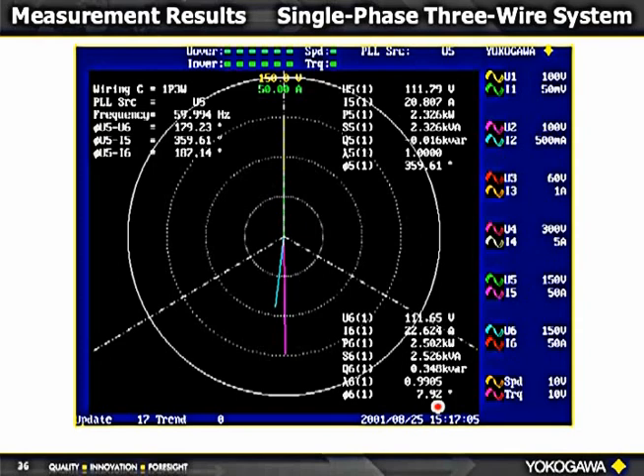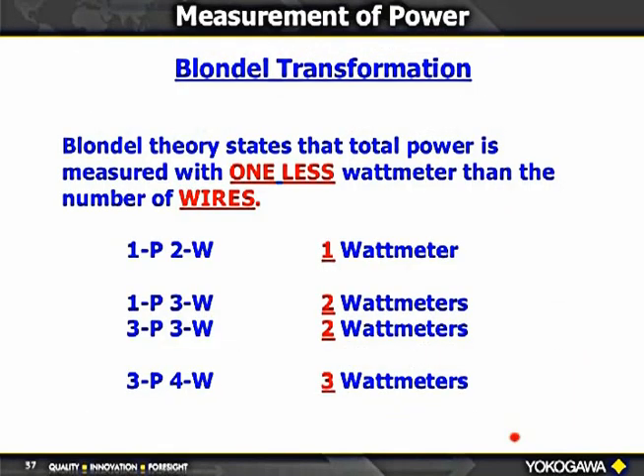The measurement of power comes back to theory by Blondell's transformation, which states we measure total power with one fewer wattmeter than the number of wires in the circuit. Single-phase two-wire: one wattmeter. Single-phase three-wire (split-phase): two wattmeters. Three-phase three-wire: two wattmeters. Three-phase four-wire: three wattmeters. Blondell proved this through vector analysis and it is the standard by which everyone operates.